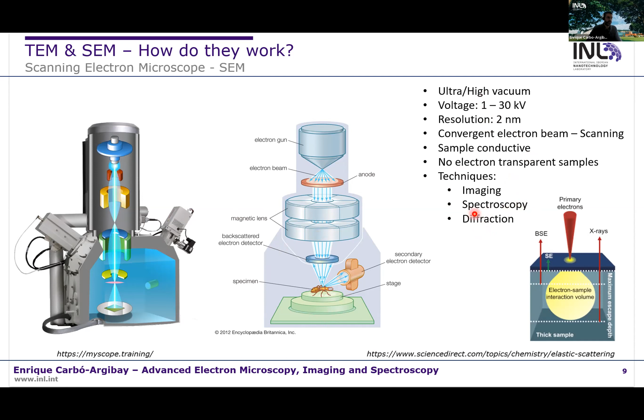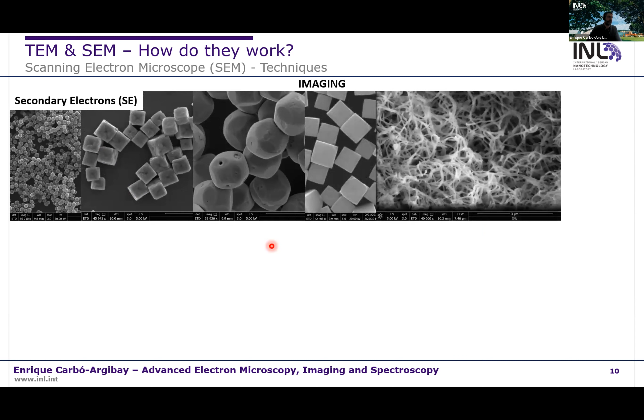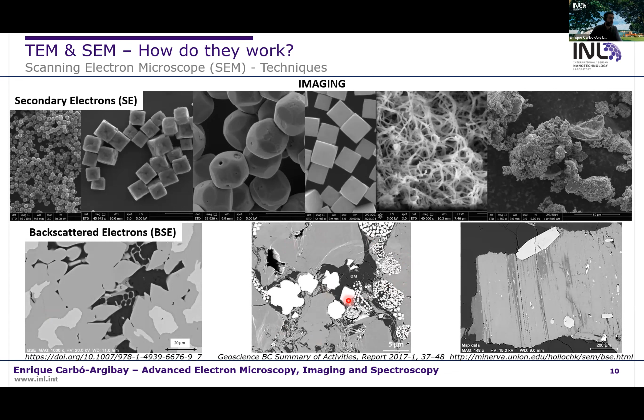And the information we can get from the sample in this case can be an image, can be a spectrum, or can be a diffraction pattern. As you can see here, we can characterize different types of nanoparticles, catalysts, fibers, or even analyze cross sections of different materials. The different contrasts we can see here tell us that the sample has a different chemical composition, and this can be confirmed with spectroscopic techniques in the scanning electron microscope. So we can combine the imaging mode with the spectroscopic mode. As we can see here, this is an image of the SEM, and we can overlap this image with the spectra and determine that the different contrast comes from different composition.